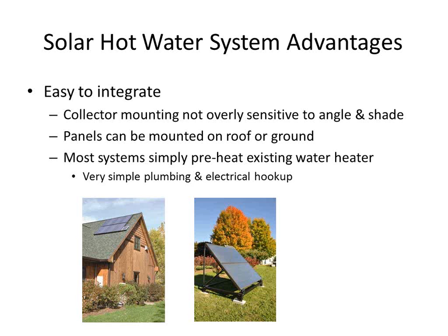I continue to be amazed at how many people confuse the physics of photovoltaics with the physics of solar thermal heating. Whereas photovoltaic panels are very sensitive to shading - to partial shading - the drop-off rate is fairly high as the sun moves off the normal incident angle from the collectors, partial shading for a solar thermal panel really isn't a factor. If you shade 10% of the collector, you're going to get 10% less power, not 90% less. And the energy drop-off for most collector technologies, when you get off normal, is not that rapid.